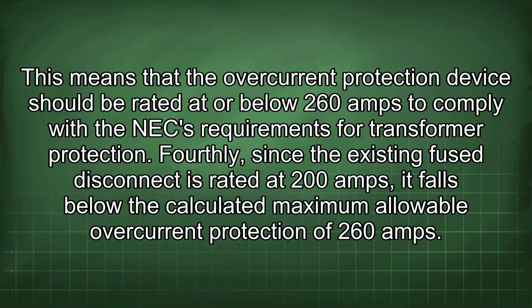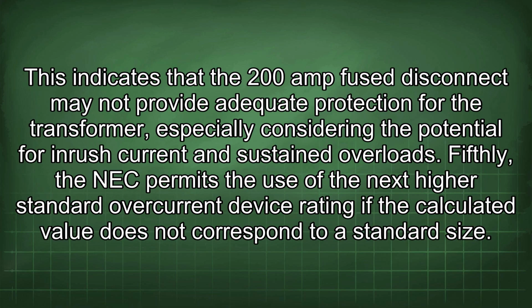requirements for transformer protection. Fourthly, since the existing fused disconnect is rated at 200 amps, it falls below the calculated maximum allowable overcurrent protection of 260 amps. This indicates that the 200 amp fused disconnect may not provide adequate protection for the transformer, especially considering the potential for inrush current and sustained overloads. Fifthly, the NEC permits the use of the next higher standard overcurrent device rating if the calculated value does not correspond to a standard size.